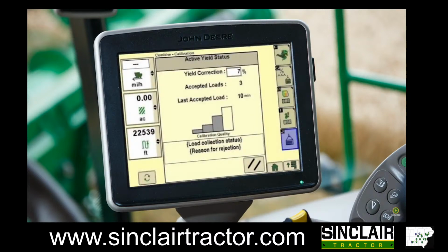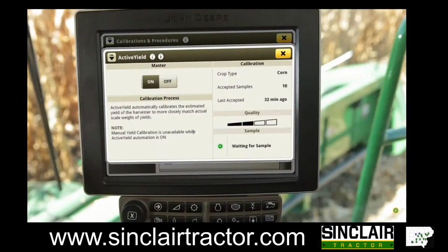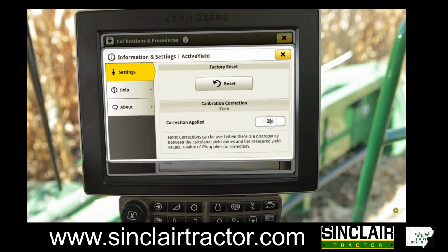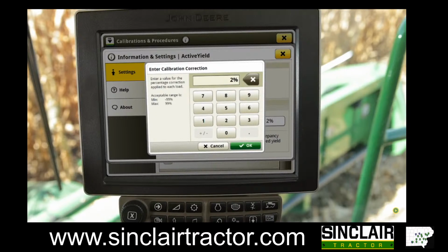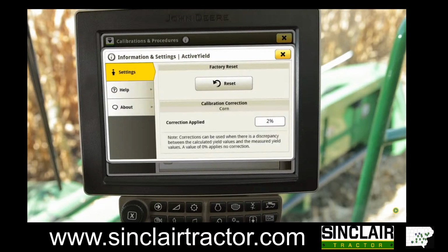Then select Accept. To enter a correction value on a 4600, go to the Active Yield screen and press the Information button. Enter the correct offset between the actual measured value and the displayed value and press OK. If the system yield is low, add a positive offset. If the system yield is high, add a negative offset.